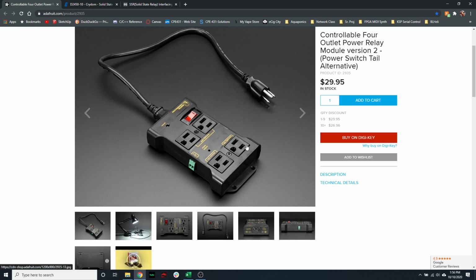That's 1460 watts on 120 volt AC. At that surge load, you're looking at 400,000 cycles that these relays are good for. They're mechanical, so they click on and click off, but if you have like a 600 watt surge, you could get 2 million plus cycles. It's just annoying the sound it makes, but it totally works, and it's $30 for 3 channels of AC control. Two of them are normally off, so you have to energize the coils to turn them on. One is normally on, and you have to energize its coil to turn it off. So they give you a little spread there, but you can hook whatever you want up to that and turn it on and off.